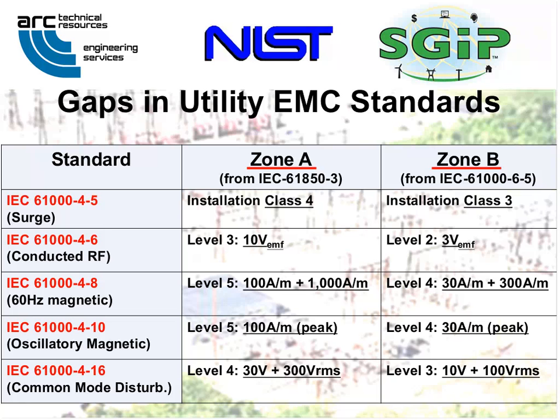Zone B is defined in the document 1613.1 as outside the substation fence, out in distribution. And it's one level lower in every case, right from 61000-6-5, the generic standard for power equipment immunities in the European Union. So with that, I'm going to move into now what I call the boring content part of the presentation, where I'm going to actually go through these five tests, hopefully as quickly and painfully as possible.